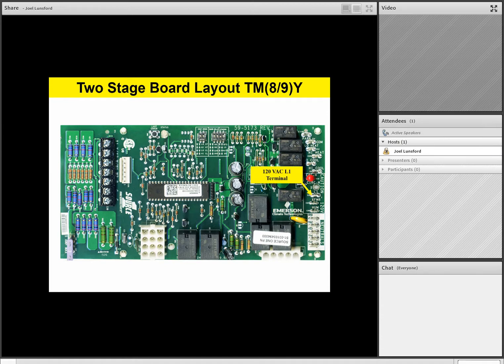XFMR is our terminal to power up the transformer. Right below that is a HUM terminal, that 120 volt humidifier. If a humidifier is desired, that will be energized during the heating mode. Right below that is a fairly large bank of neutral terminals. Those neutral terminals, by the way, are all tied together electrically, so you'll notice that the white wires for your 120 volt components, like your transformer and your motor and so on, will all tie into those neutral terminals. At the bottom of the board, we have an output harness to the hot surface igniter and inducer fan motor, and again, that'll all be harnessed in from the factory.